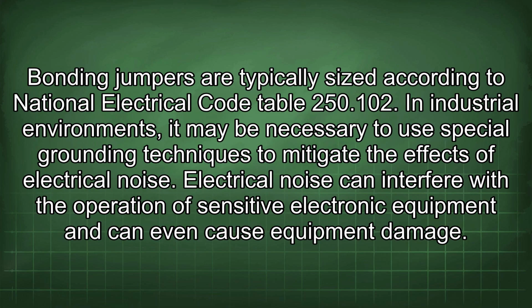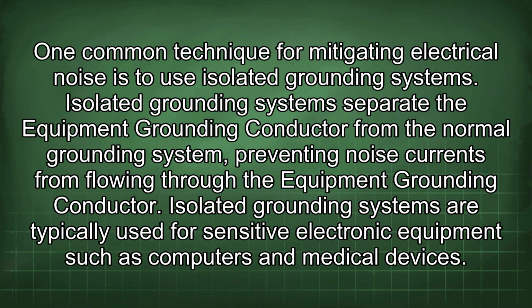Bonding jumpers are typically sized according to National Electrical Code Table 250.102. In industrial environments, it may be necessary to use special grounding techniques to mitigate the effects of electrical noise. Electrical noise can interfere with the operation of sensitive electronic equipment and can even cause equipment damage. One common technique for mitigating electrical noise is to use isolated grounding systems. Isolated grounding systems separate the equipment grounding conductor from the normal grounding system, preventing noise currents from flowing through the equipment grounding conductor. Isolated grounding systems are typically used for sensitive electronic equipment such as computers and medical devices.